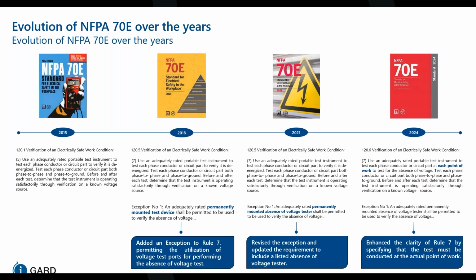In 2015, the only option to verify an electrically safe working condition was to use a multimeter to test the phase conductors or circuit paths directly. This requires opening the door to an electrical cabinet with appropriate safety equipment and making direct contact. In 2018, Clause 120.5 was introduced, and with the exception 1 to Rule 7, permitting the utilization of voltage test ports for performing the absence of voltage test. In 2021, Clause 120.5 was revised and exception 1 was updated to include a permanently mounted listed absence of voltage tester. The 2024 revision enhanced the clarity of Rule 7 by specifying that tests must be conducted at the actual point of work.